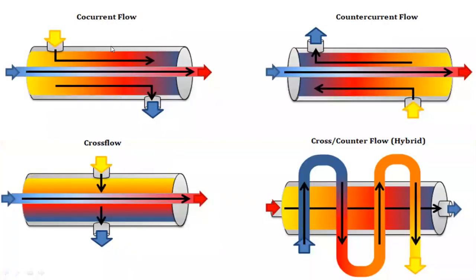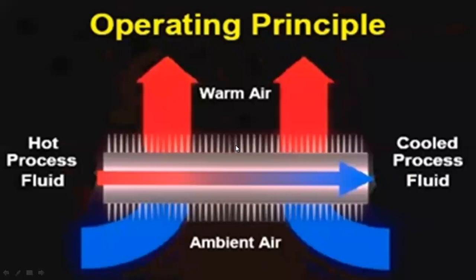There are different flow configurations. In co-current flow, both fluids — tube side and shell side — flow in the same direction. In counter-current flow, the shell side fluid flows opposite to the tube side flow. In cross flow, the tube side goes in one direction and the shell side comes perpendicular. Finally, cross and counter combined flow is called hybrid flow, where the shell side fluid goes one way and the tube side fluid goes both up and down.